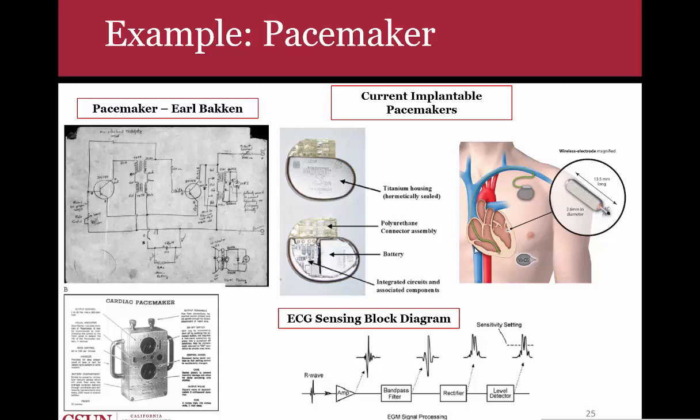And so I forgot to mention that a person that has an arrhythmia typically has some problems with the conduction pathways of their heart. So you have to stimulate specific portions of the heart to resynchronize their heartbeat. To do that, you'd have the external stimulator hardware in a can that's underneath the skin. You would then get the lead, and you would put it through the vasculature and run it into the area where you want to stimulate.